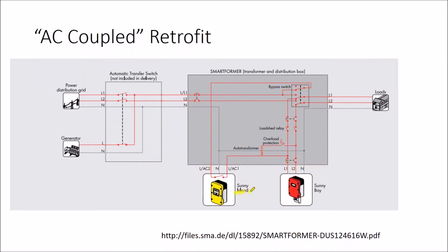It's more elegant if they can do that through digital communication, but it doesn't have to be digital. So if you have a solar array and want to add a battery bank to it, while it's nice to stay within the same brand, all you really need to do is add a battery inverter and a transfer switch, and you're good to go.